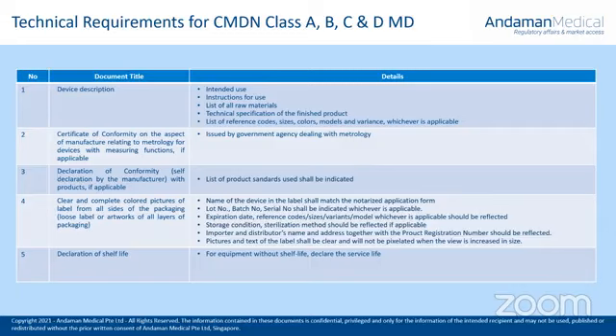Device description. You can usually find it in your IFU or the instruction manual of your device. It includes the intended use, instructions for use, list of raw materials, technical specifications of the finished product, and the list of reference codes, sizes, colors, models, and variants, whichever is applicable. Next, the certificate of conformity on the aspect of manufacture relating to metrology for devices with measuring functions. There are medical devices that have measuring functions. This is quite different from the third requirement, which is the declaration of conformity.